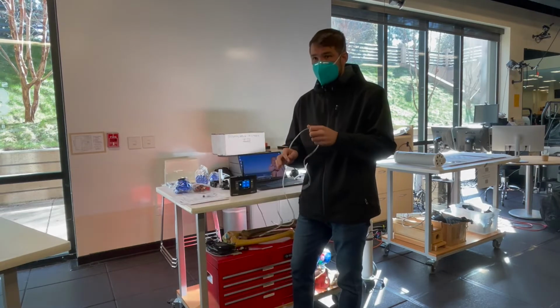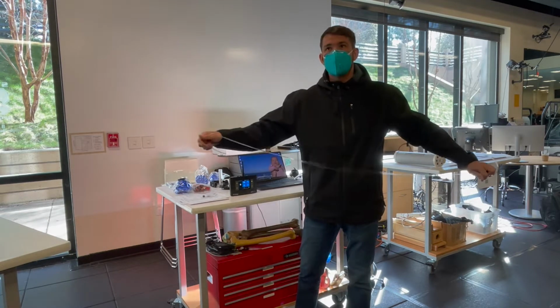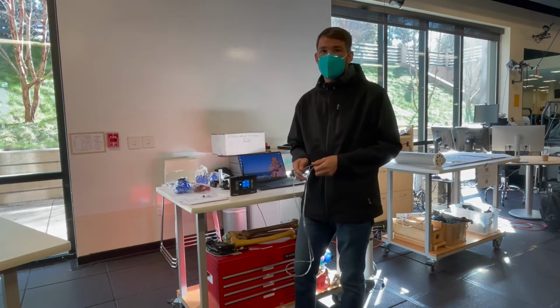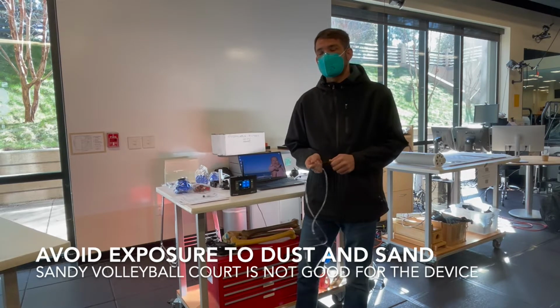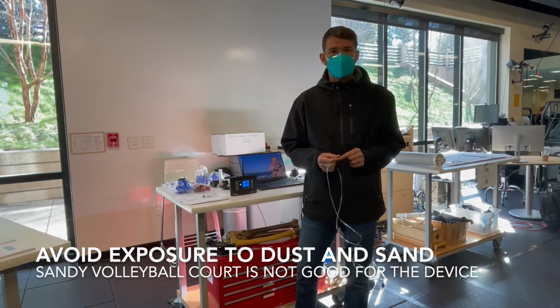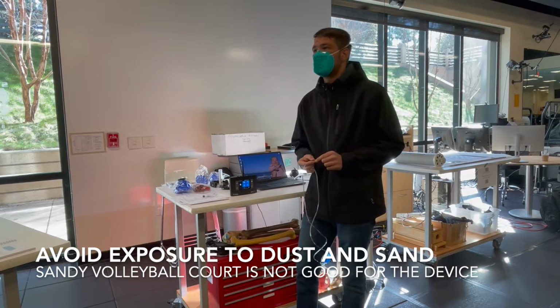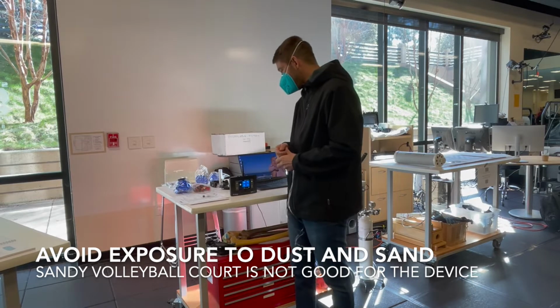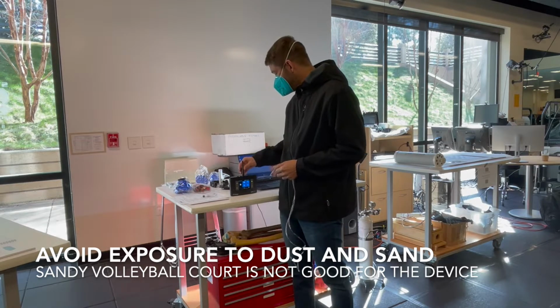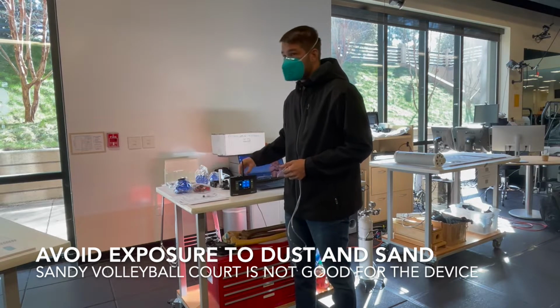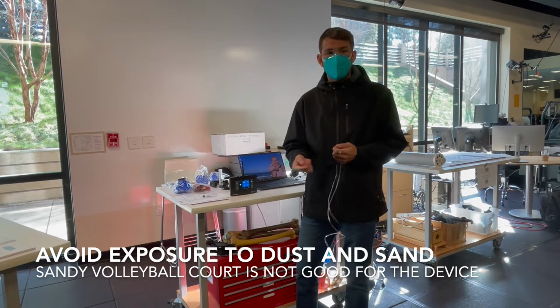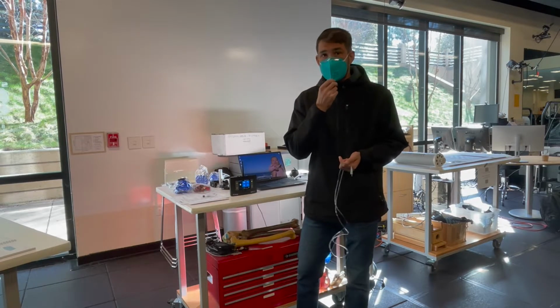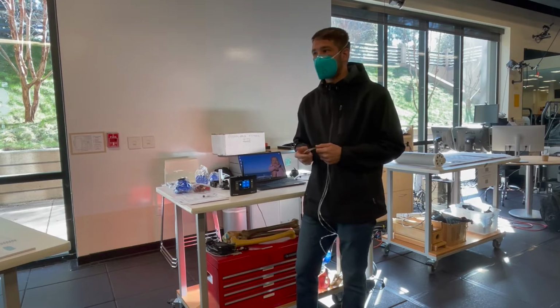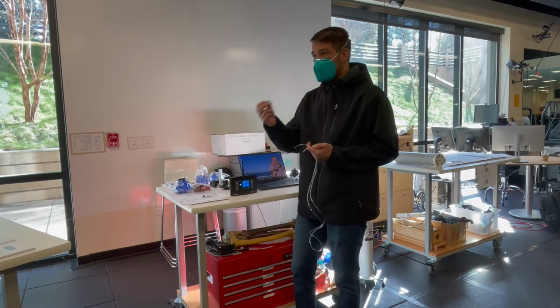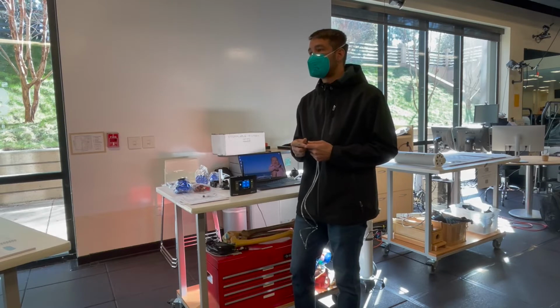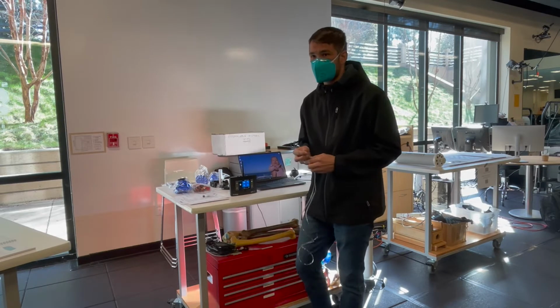Yeah. In very dusty environments, it's fine if you're in an open field and a little bit of dust gets kicked up, but if there are super high winds and a bunch of dust in the air, you might want to be careful too, just because that open air circuit, even though it's covered by this mushroom cap, you don't want dust to get sucked in there. There are filters that prevent dust and dirt from entering the sampling circuit, but those filters can get clogged, and then you'll have issues with calibrating and obviously running tests, and then the filters need to be changed.